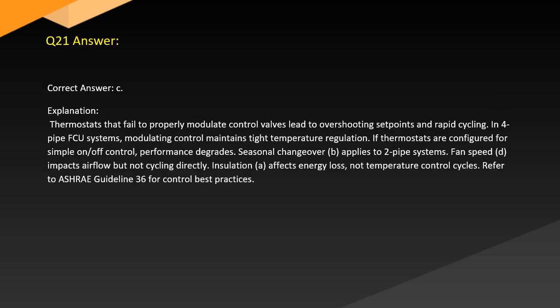Answer. Correct answer: C. Explanation: Thermostats that fail to properly modulate control valves lead to overshooting set points and rapid cycling. In 4-pipe FCU systems, modulating control maintains tight temperature regulation. If thermostats are configured for simple on-off control, performance degrades. Seasonal changeover, B, applies to 2-pipe systems. Fan speed, D, impacts airflow but not cycling directly. Insulation affects energy loss, not temperature control cycles. Refer to ASHRAE Guideline 36 for control best practices.